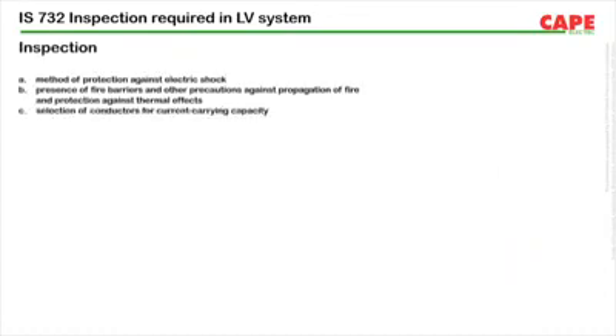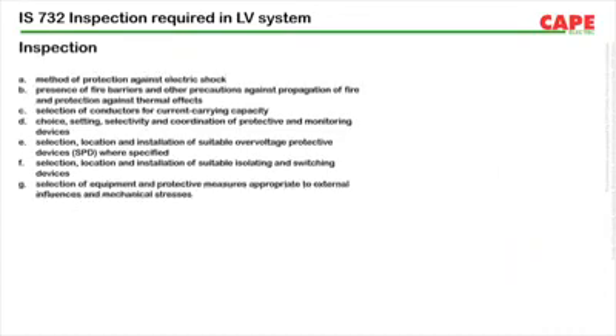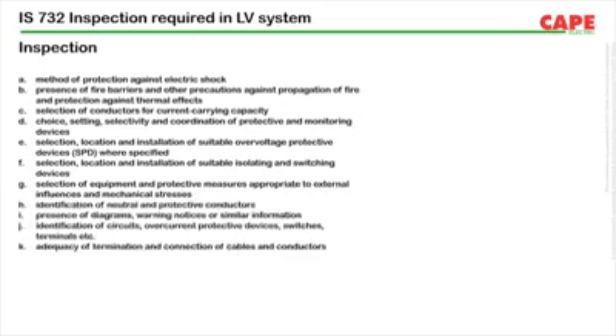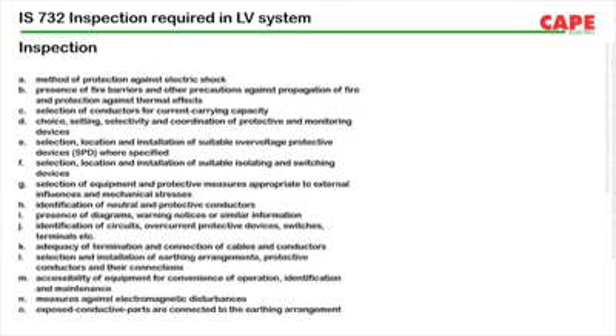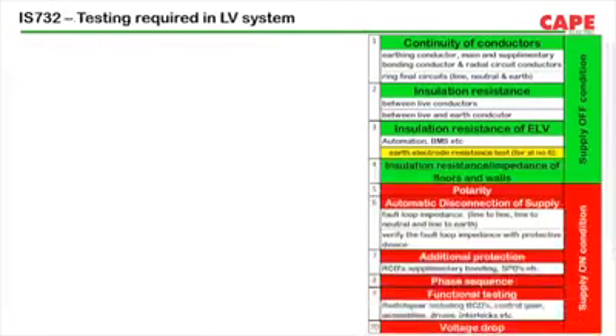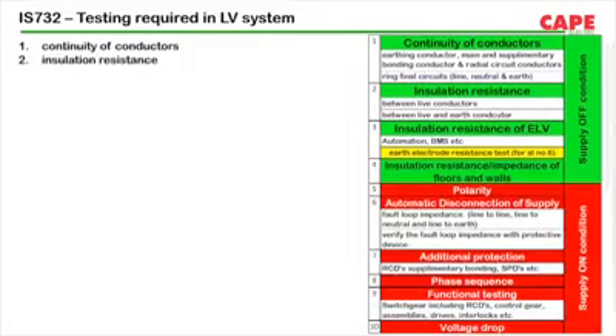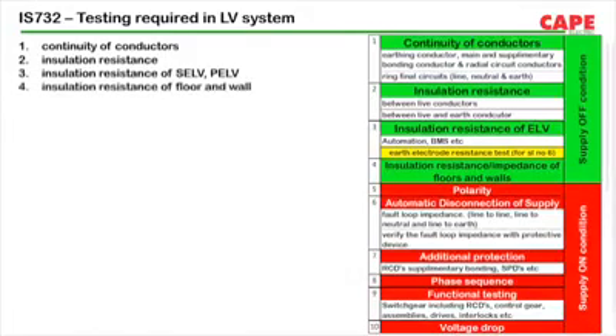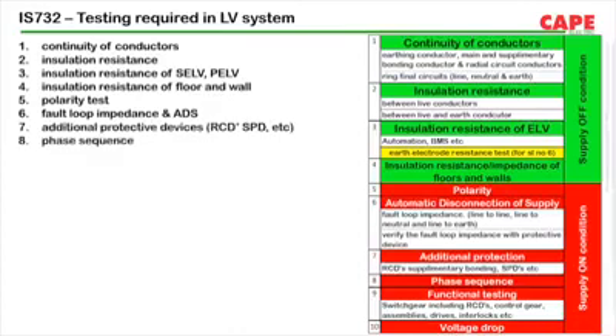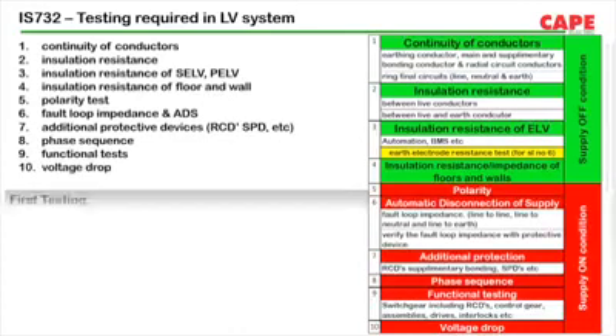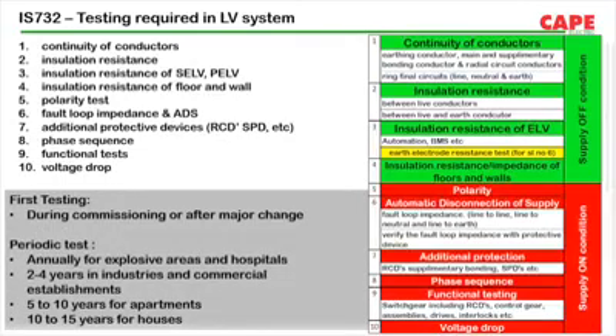Unfortunately, the practice of measuring fault loop impedance and checking the disconnection time of a protective device didn't exist in India. Even large multinational companies who do electrical safety audits don't do this measurement. As a conclusion, I would like to make a statement. The subject of electrical safety in low voltage systems doesn't exist in India. In the safety seminar, we speak about good quality protective devices and good quality wires. But the basics of low voltage electrical safety are neither understood nor followed in India.